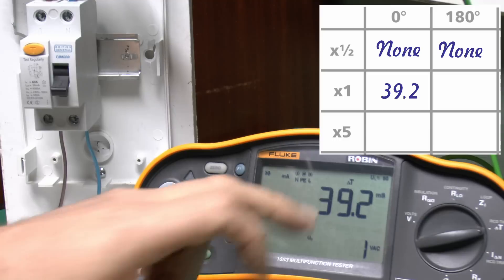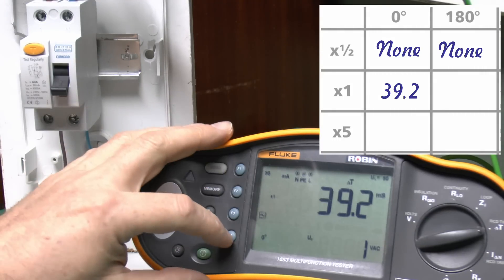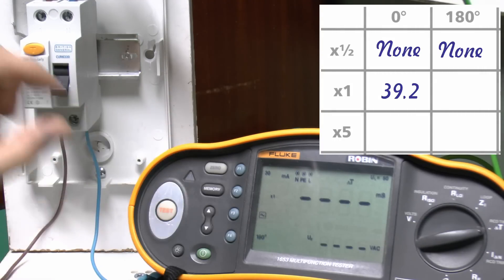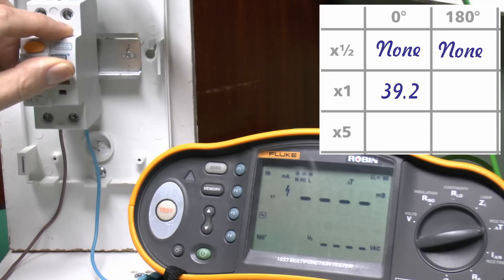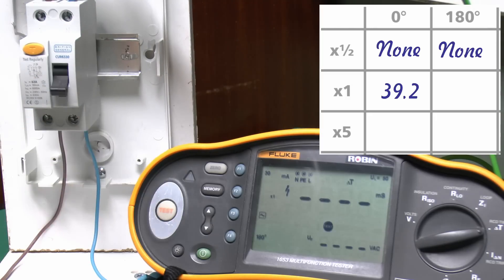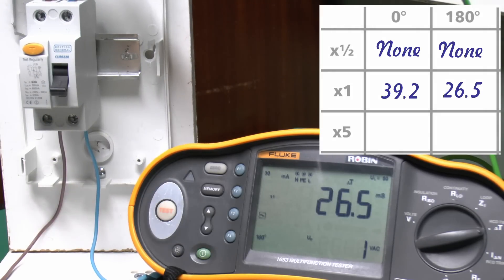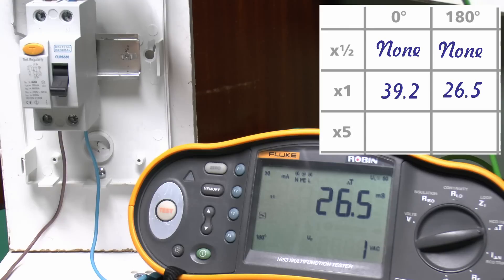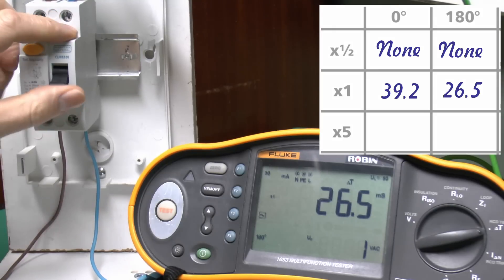So there we have the result there of 39.2 milliseconds, and again, we'll try that again on the 180 setting, and that case 26.5. So in both cases, that's well within the 200 or 300 in this case setting there, so no problems with that.